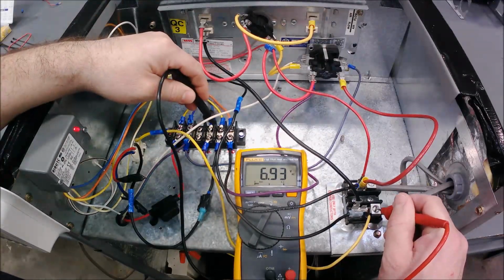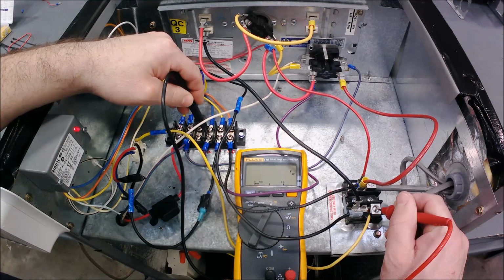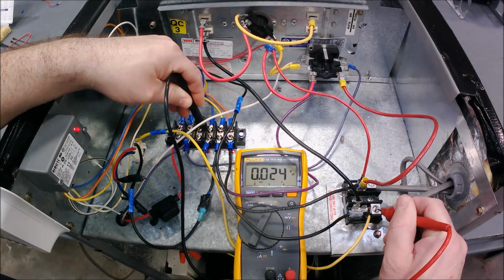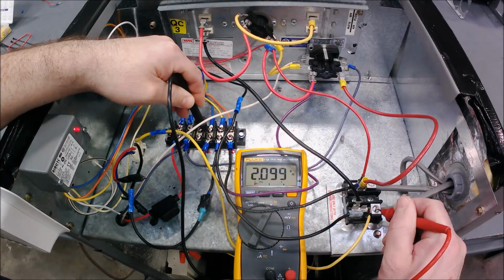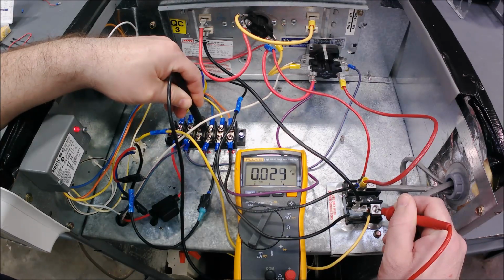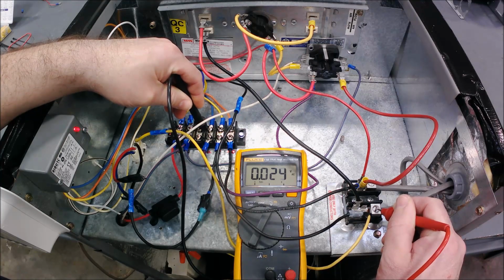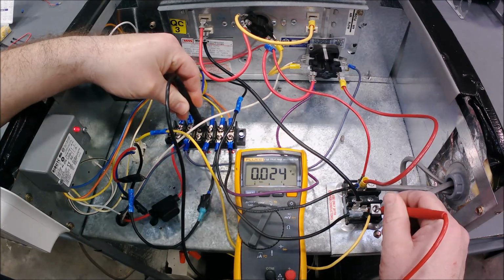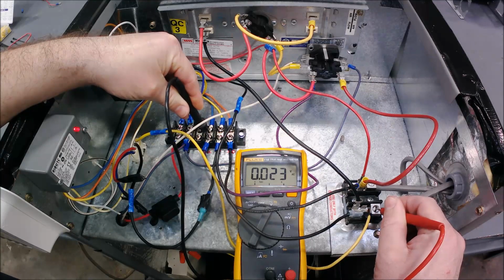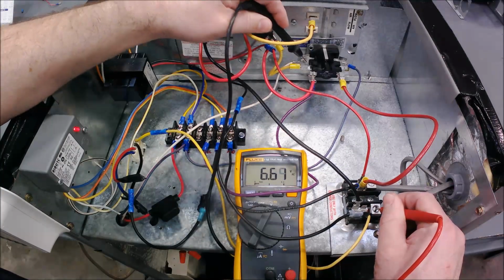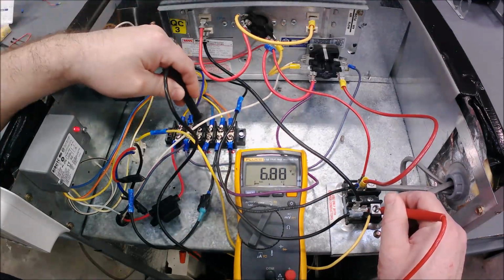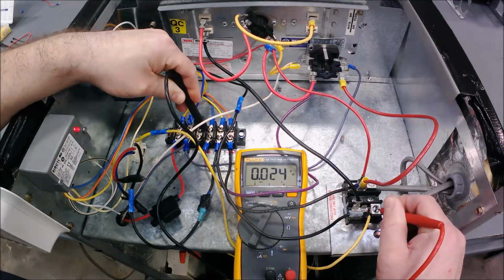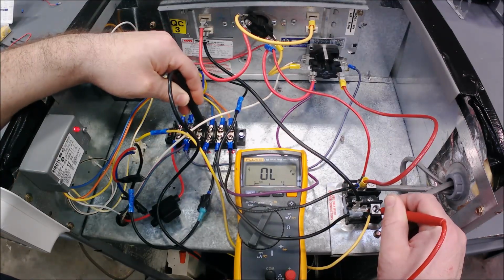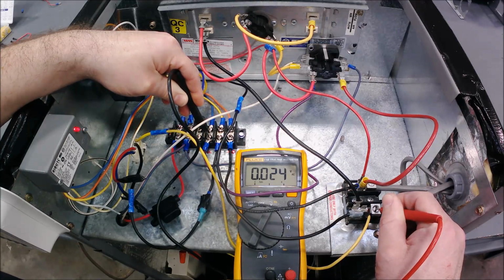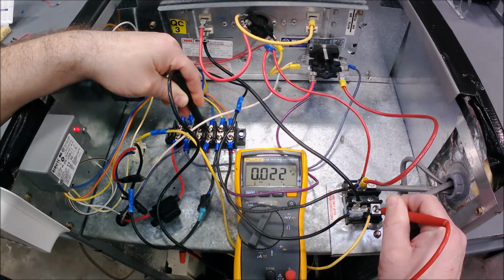But look what happens when I check the other one. 0. Why? Because this normally closed leg over here has no power on it right now. There's voltage there, but the way that we're reading it, we're on the same side of power, because we're backfeeding actually through this heat sequencer, and it's checking the L2 side. So L2 to L2, if I'm checking in this situation, is 0. No difference. Doesn't mean no power, means no difference.